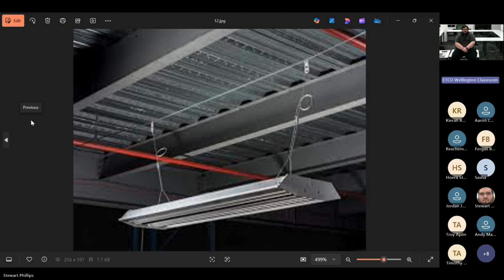Weight? Yep, definitely. The amount of cables heading up at the cables, the weights. Where to mount the cable. Fixings at either end, yep, the span. We don't want too long of a span because we will get droops. So we generally want to make sure we're supporting the cable at least every 5 or so meters, again depending on the weight of the cables. And that weight of the cables will then determine how many cables you can put on it.